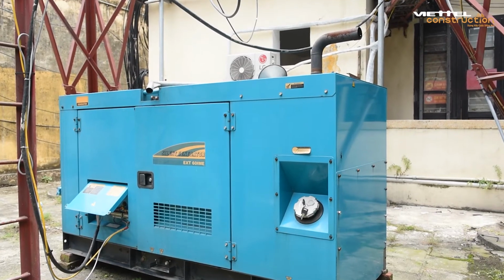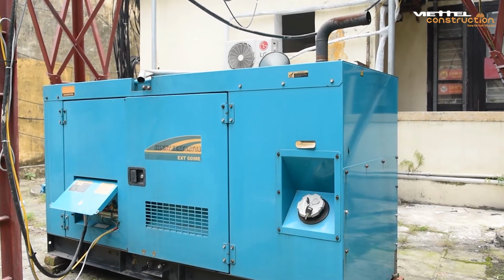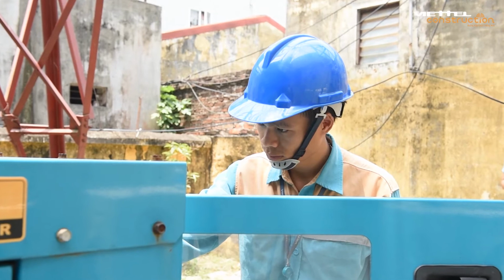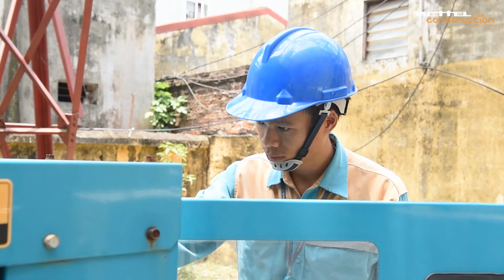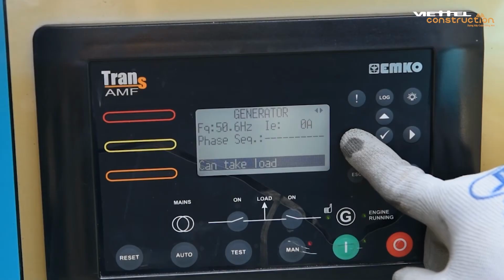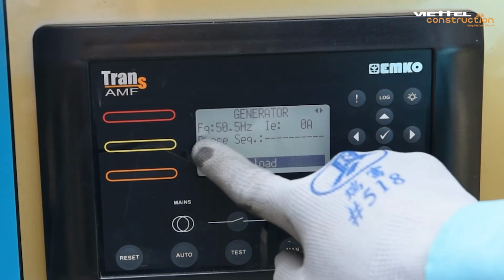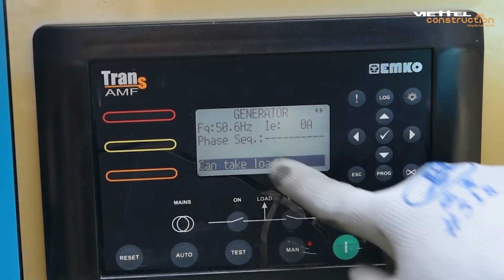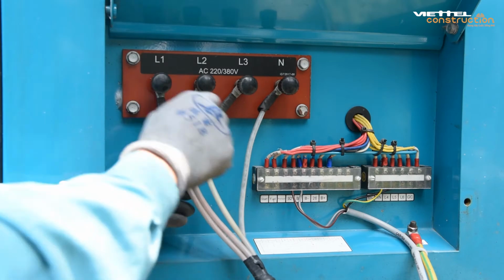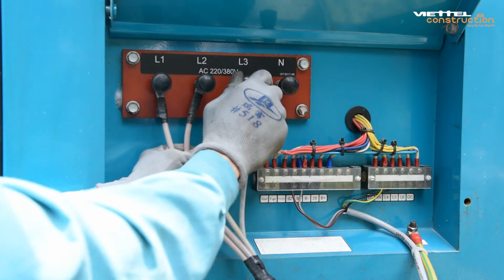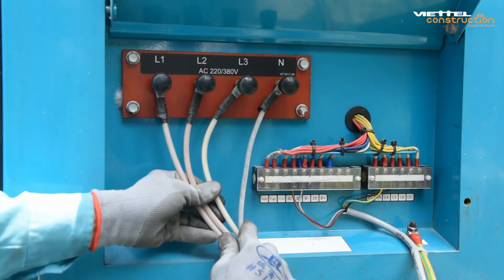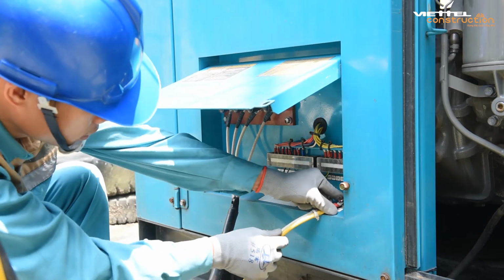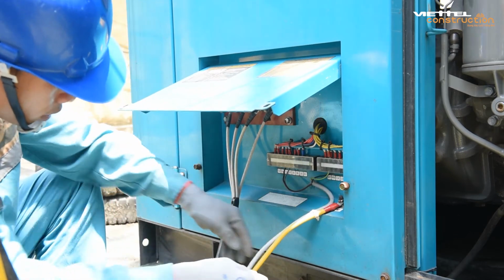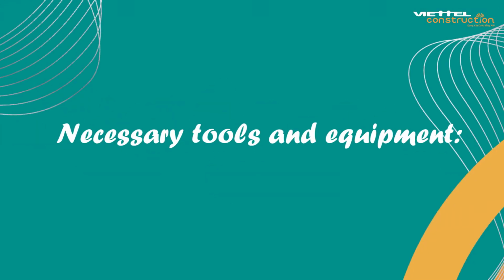The standby generator is a very important and indispensable device in replacing the national grid, helping to rescue information in the event of a power failure, ensuring and maintaining the station information system always operating in safety conditions. The following video will guide you how to operate the Kim Binh 50 kVA 3-phase diesel generator according to technical procedures. Necessary tools and equipment.